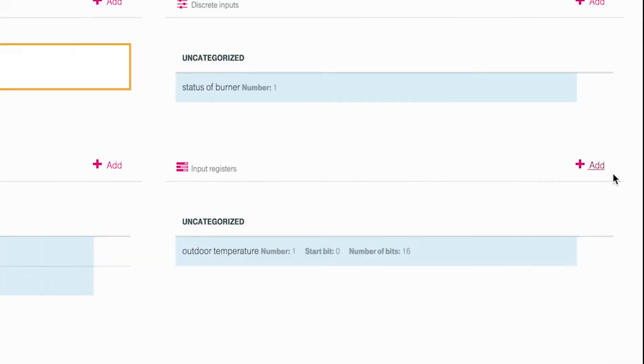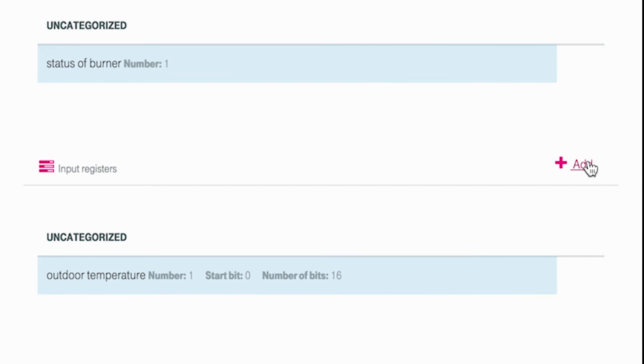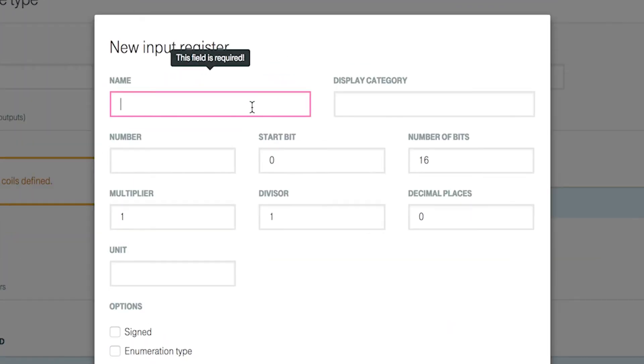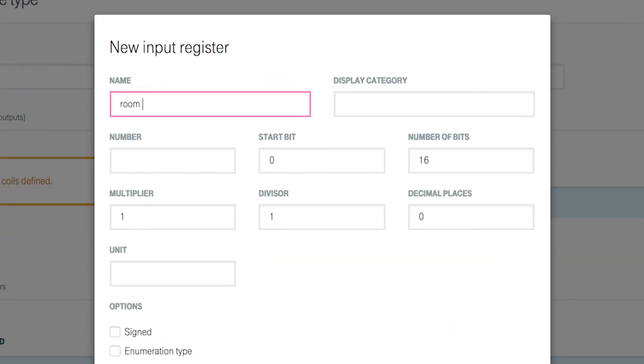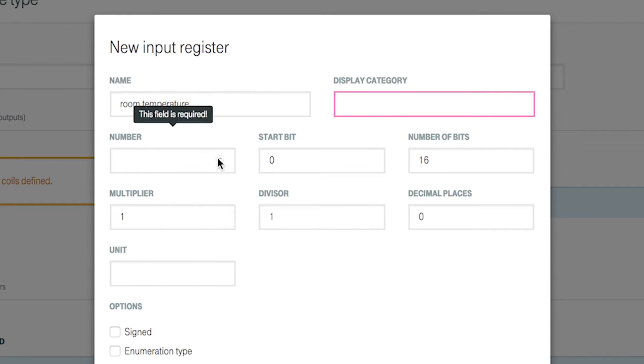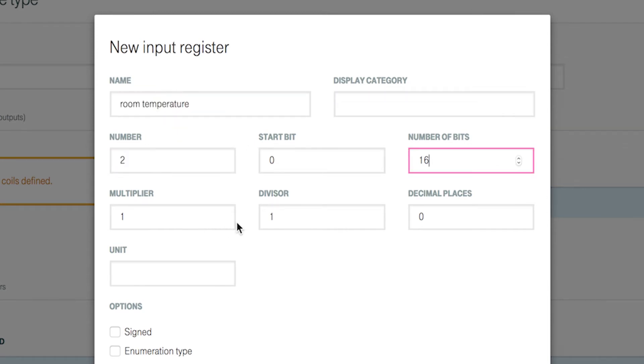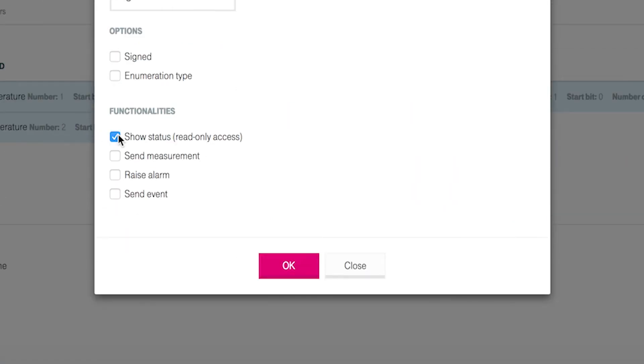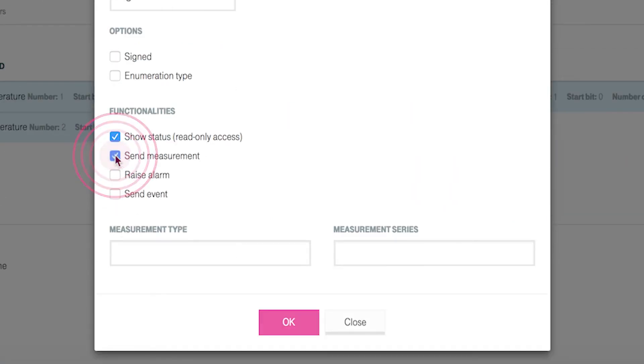Create the register for maximum temperature the same way. Create the registers outdoor temperature and room temperature analog to the steps above as input registers. Input registers can be defined only with show status because they aren't editable by the user. Because we want to show the room temperature by measurement values inside the Cloud of Things, you have to choose send measurement in the section functionalities.